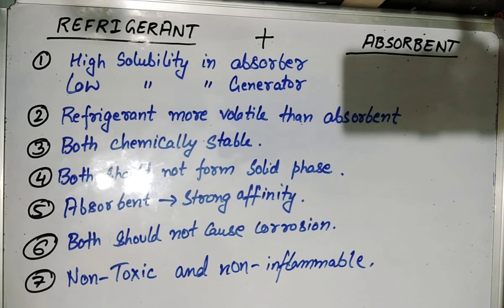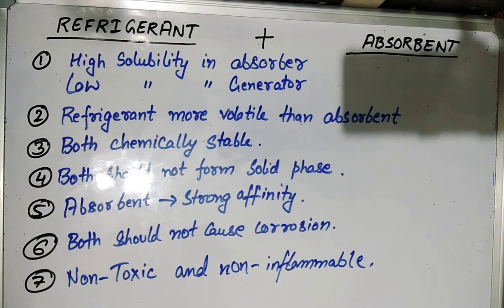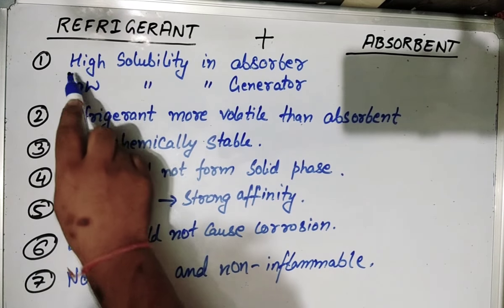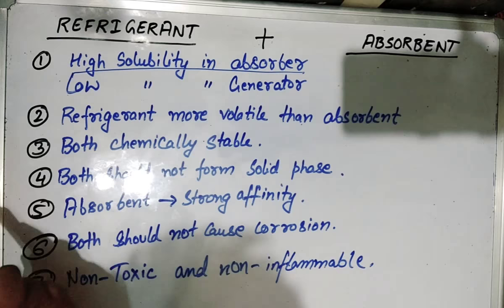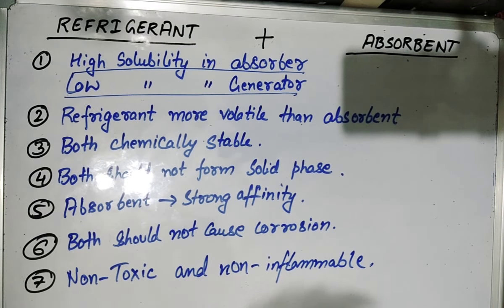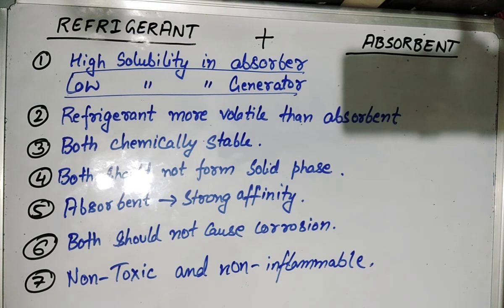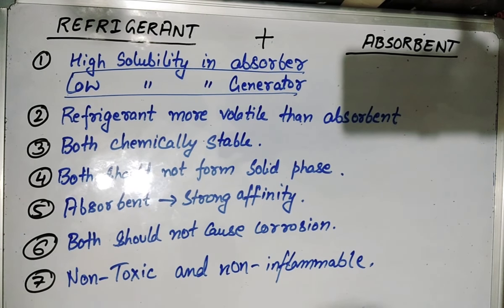Now the characteristics of the mixture of refrigerant and absorbent that should be possessed: the first thing is that it should have high solubility in the absorber but low solubility in the generator. The second thing is that the refrigerant should be more volatile than the absorbent. The third point is that both should be chemically stable and both should not form any solid phase, as it can cause blockage in the system.